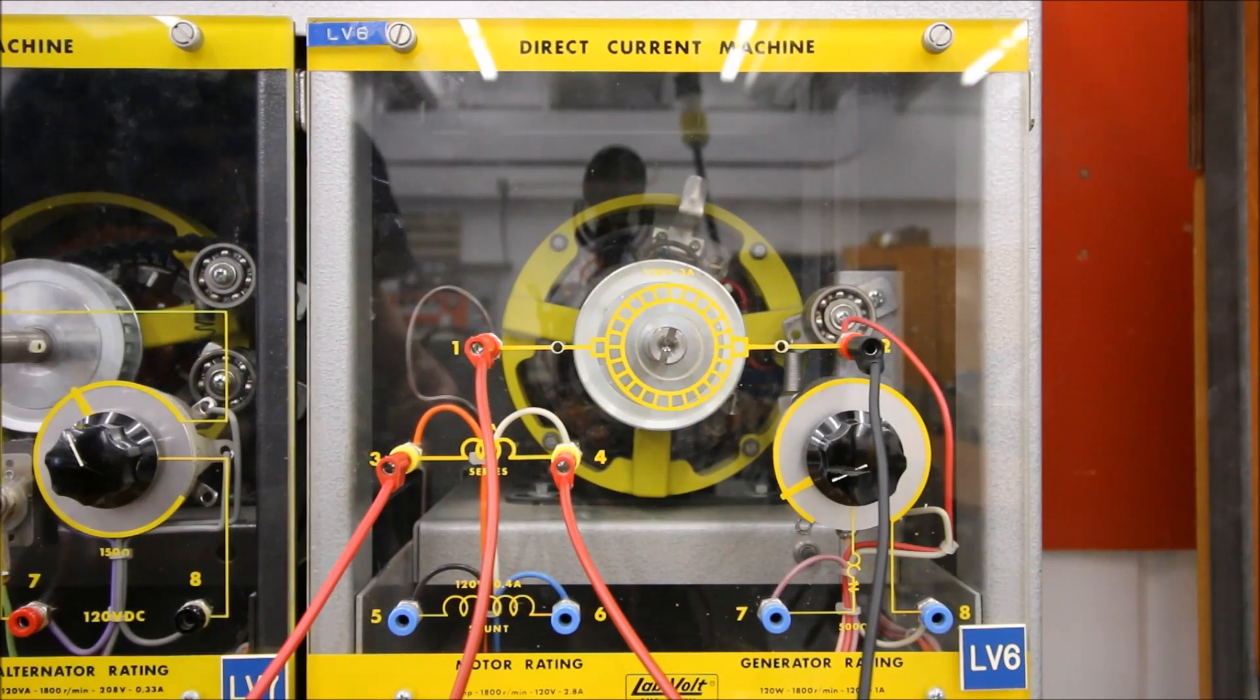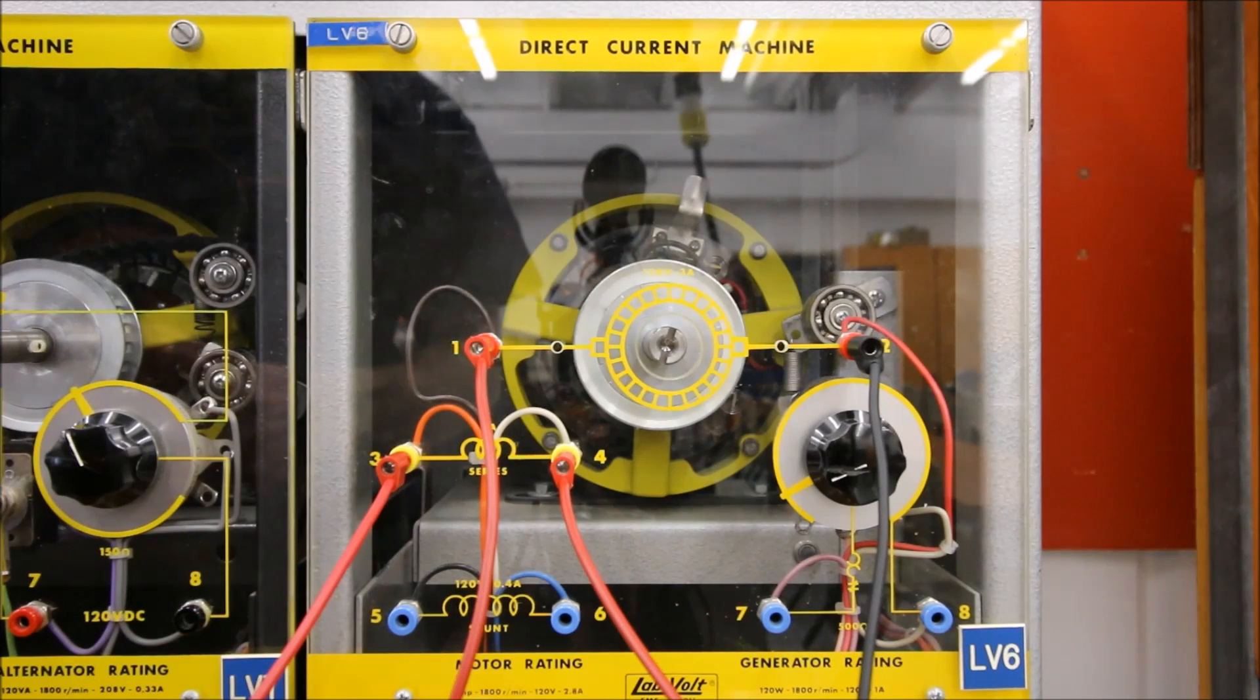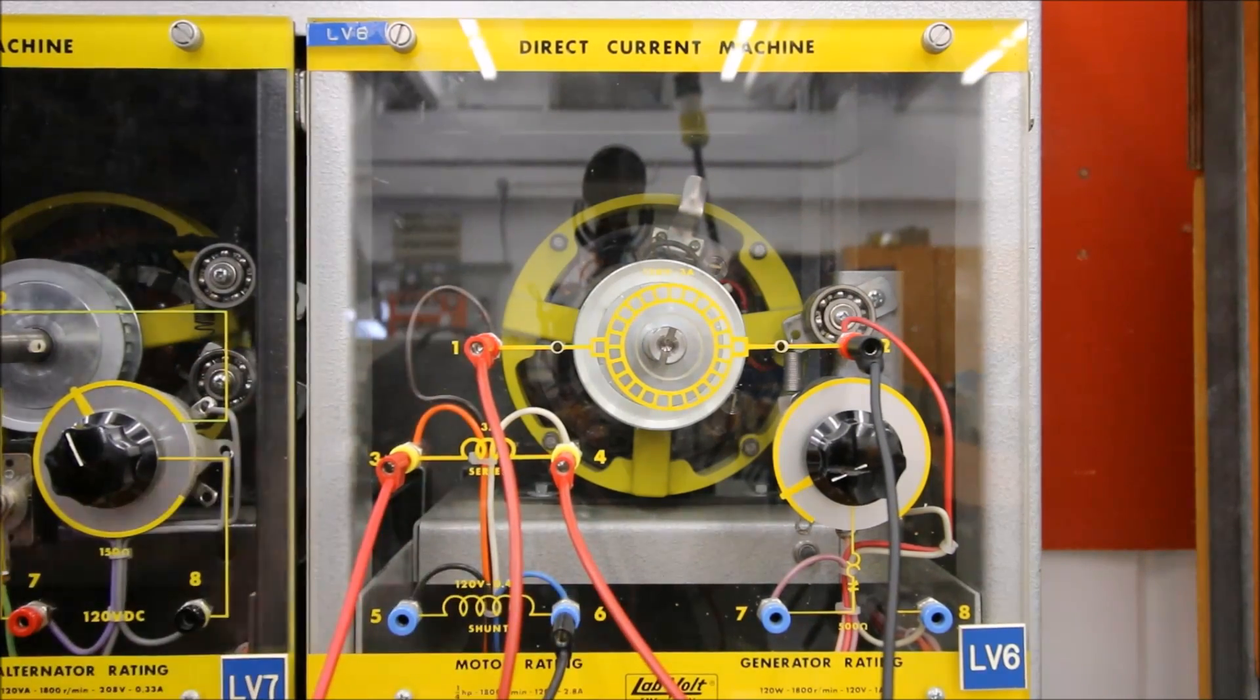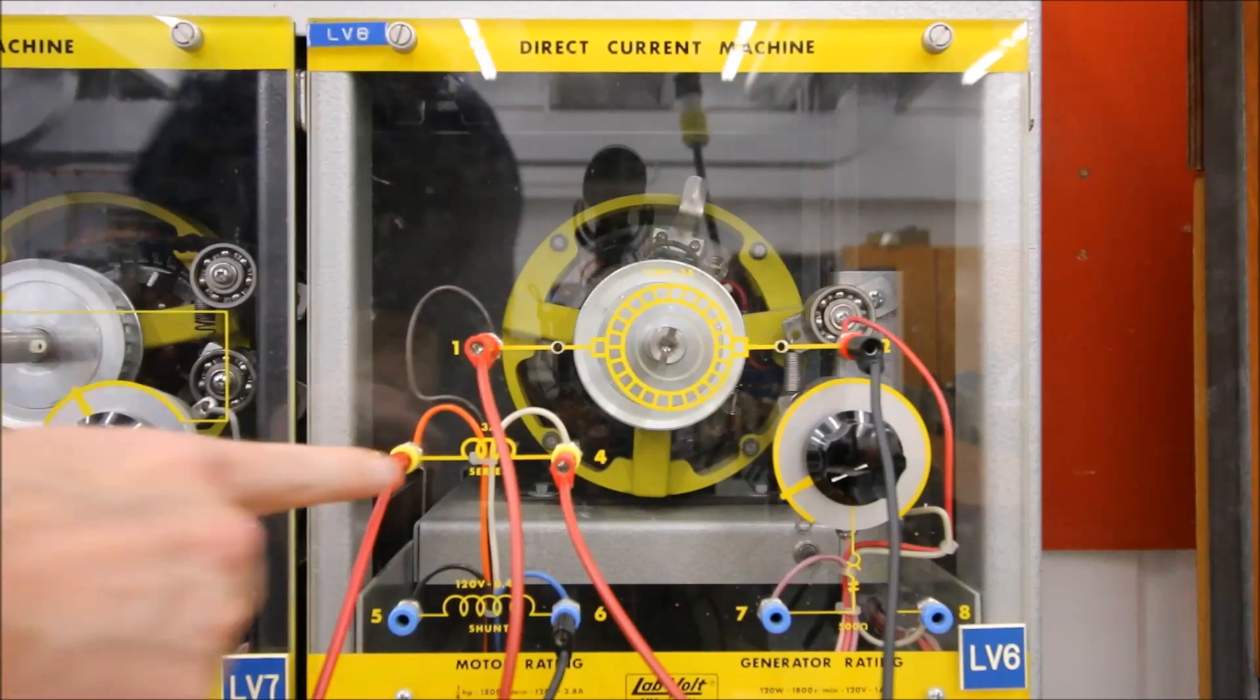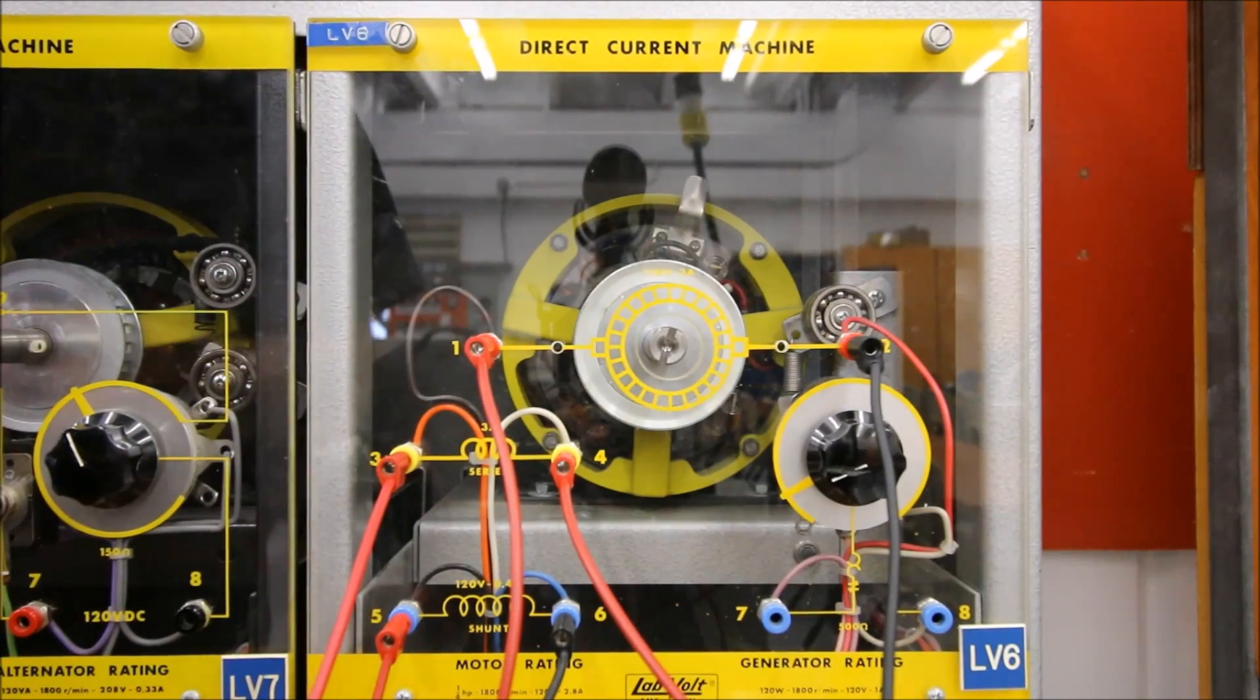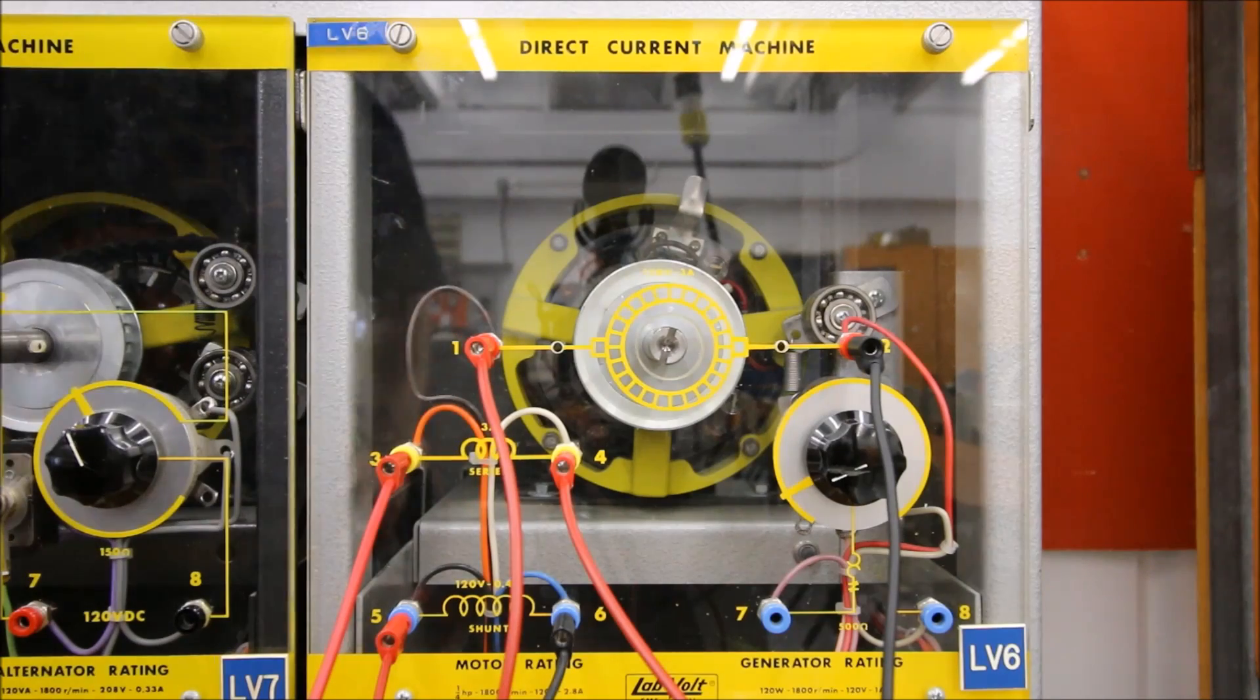In addition to that, we're going to have the shunt in parallel with both the series and the armature. So the shunt is essentially going to be right across the source. F2 is going to go to my negative, and because I've put S1 to the positive, you can see S1 is to the positive, then F1 is also going to go to the positive. That's crucial for a cumulative compound motor. Let's take a look and see how this guy sounds.